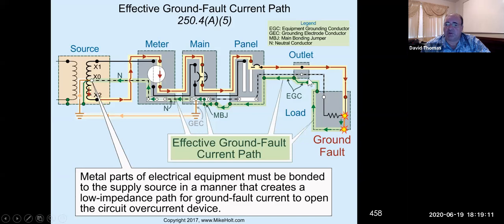So if we create a low impedance pathway, then that means low resistance, low inductive and capacitive reactance in the circuit. Then we actually create a low impedance pathway, which can facilitate the operation of the breaker. And I've said that before, the main purpose of a ground pathway is to actually facilitate the operation of the breaker. So that's another thing that we have to make sure we ensure, is that everything is grounded properly and that it is a good ground pathway back to the source, okay?